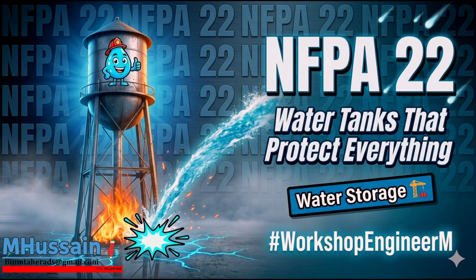Coordination with the local responders is non-negotiable, but there is a pure, unyielding limitation of physics outlined in this section that is arguably the most critical number for a civil or safety engineer designing a cistern. The depth limit. Yes. The standard mandates that the lowest water level in the tank used for fire protection cannot be more than 15 feet below the grade level where the fire truck will be parked. This is a phenomenal constraint.